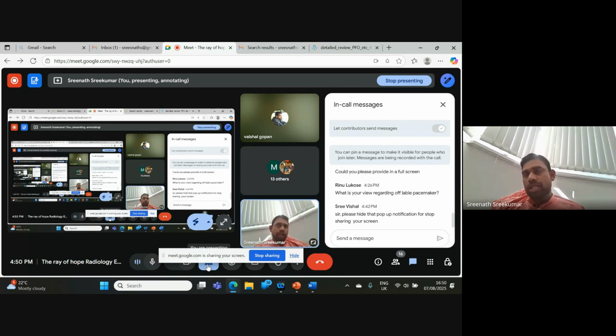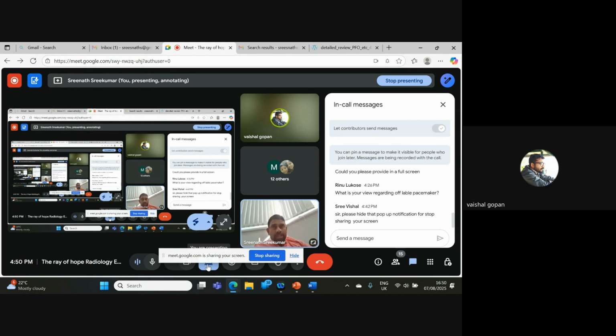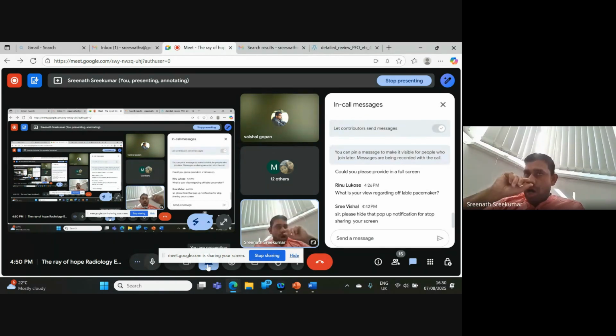If you are putting a patient inside a scanner and the implant is safe, for example a patient with a knee implant, a knee replacement, that has already been discussed under the general implant safety policy and it is safe to scan. But if you are scanning the knee and you don't use normal mode, you are giving a higher SAR level to the region, and it can cause burning. If the implant manufacturer does not specify scanning at 4 watts, and you scan with 4 watts instead of 2 watts, it can cause issues.